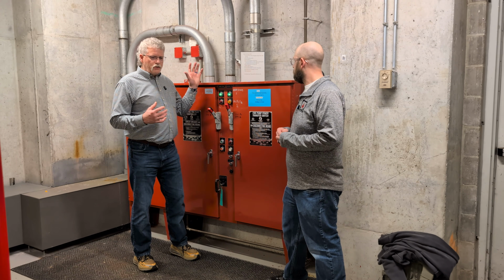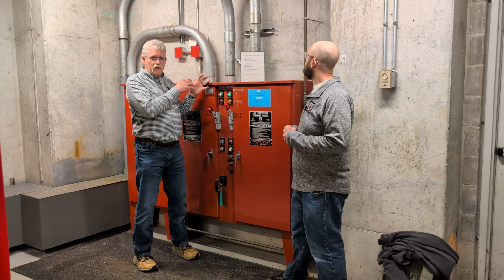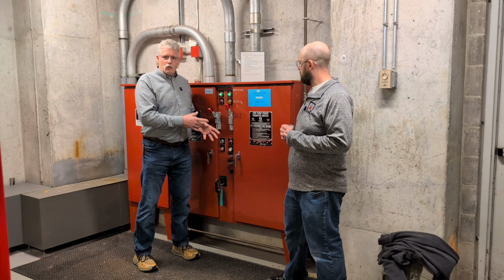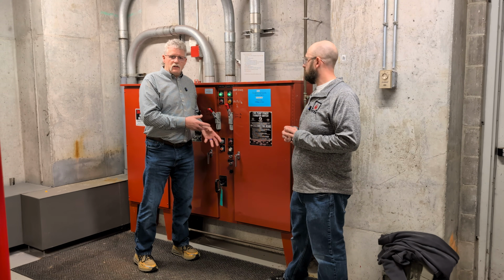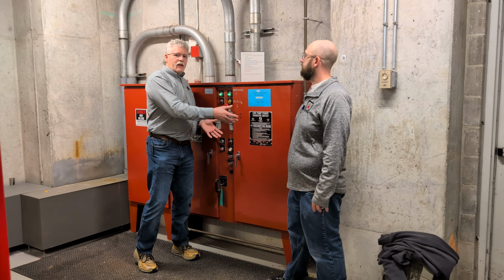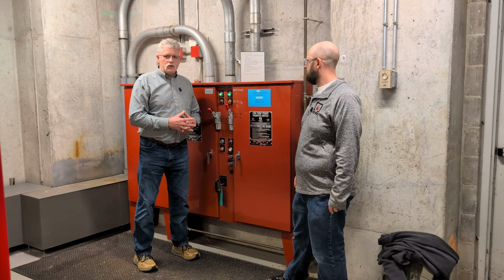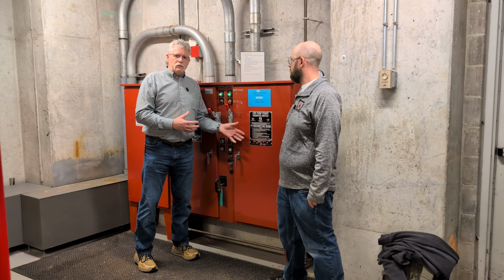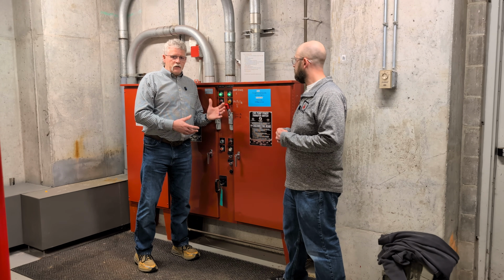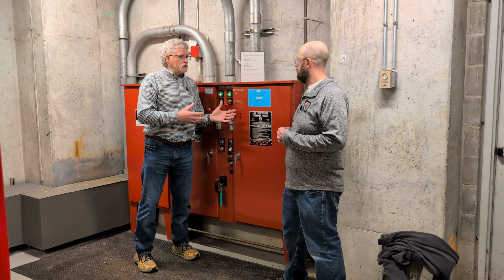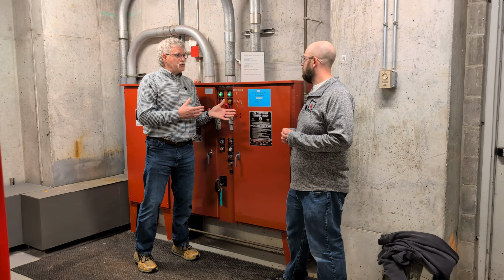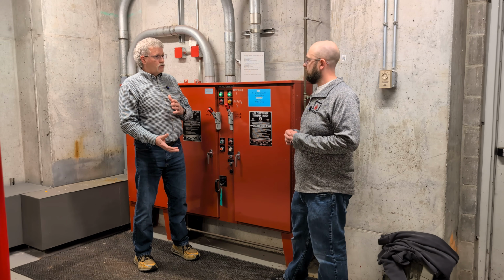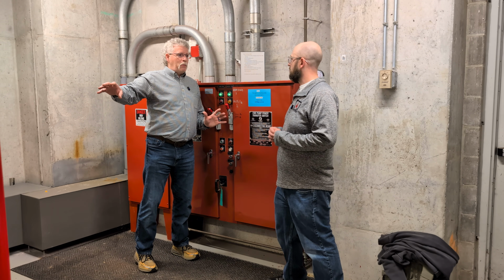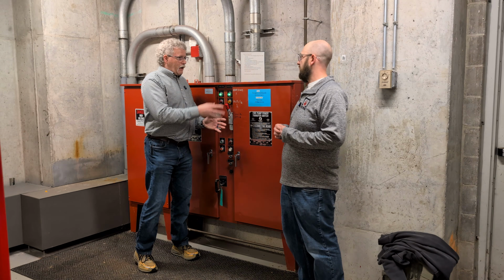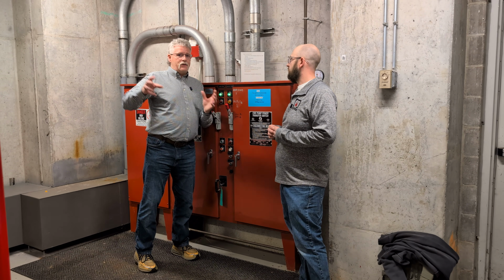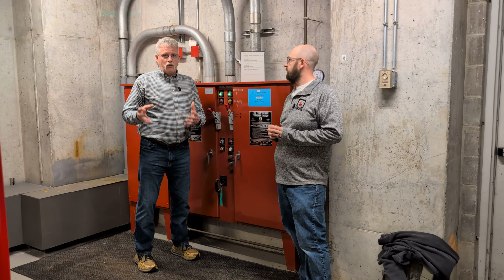The line voltage from the utility would come in at the top, and at the bottom would be the load going to the fire pump. In the middle is typically where the emergency or alternate source of power would come in. It monitors the flow of electricity from the utility side, and when it sees an interruption, it automatically switches over, even if the pump's not called to run, so that if the pump is called to run, it will turn on without delay.